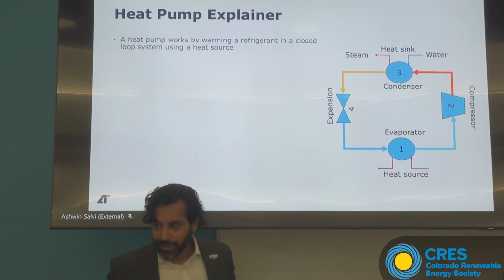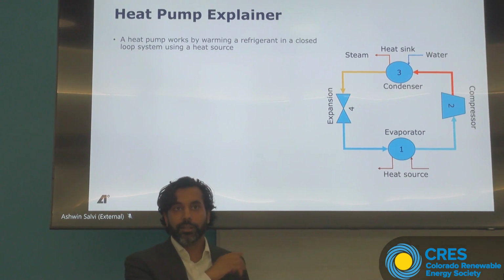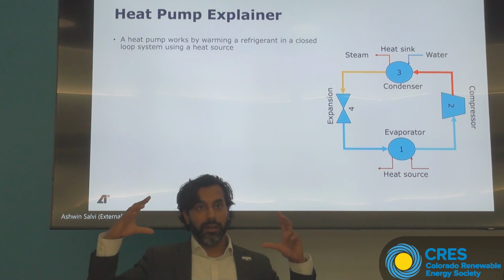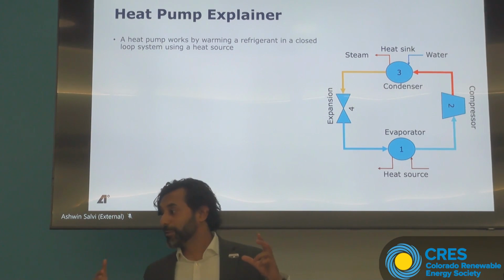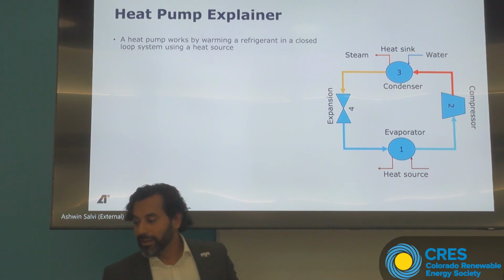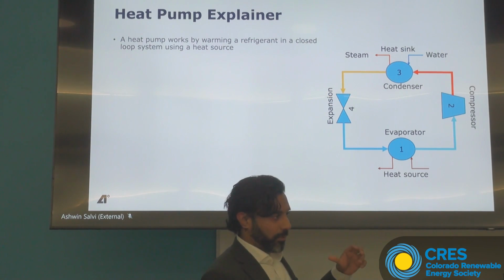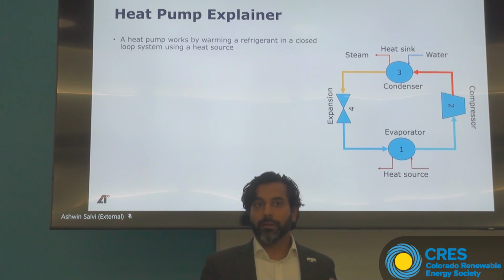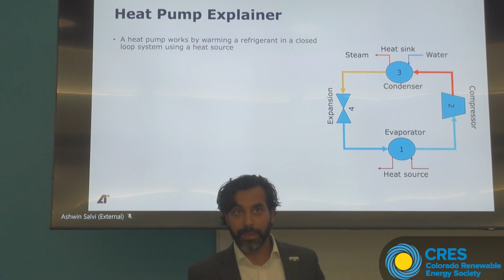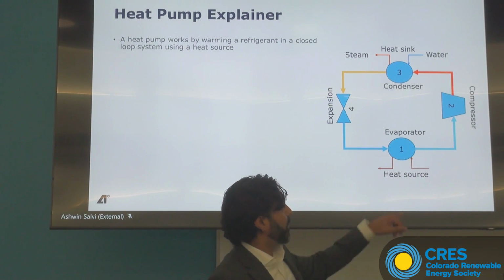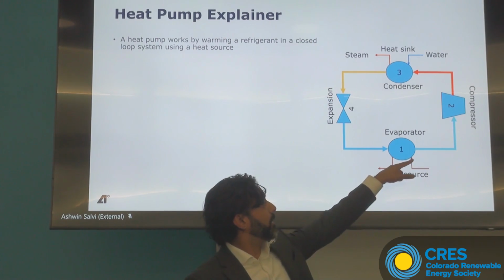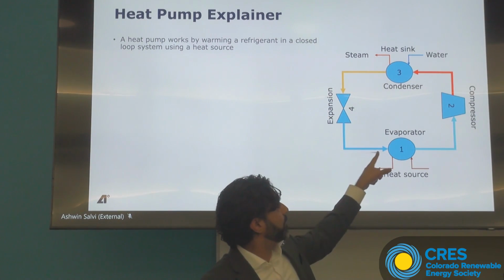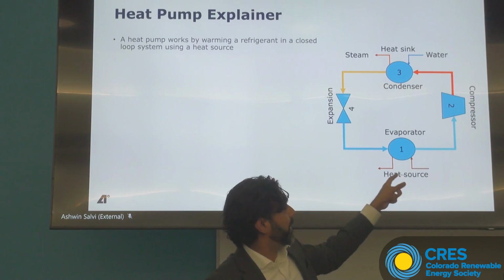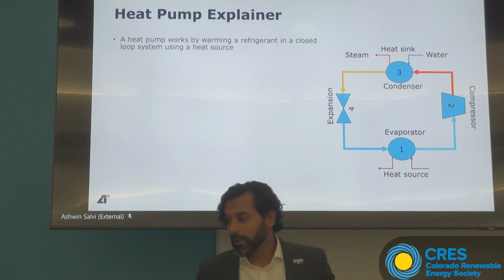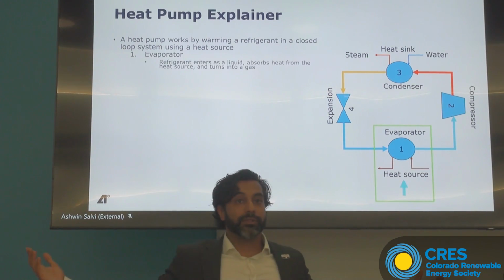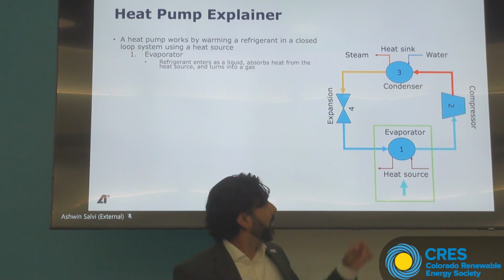So, sorry - a heat pump based system is a closed loop of refrigerant inside three or four different devices. Thank you for checking, or making sure I don't trip again. What we're doing here is sourcing heat from a certain location. Maybe a lot of you are familiar with air-sourced heat pumps that make hot water or something like that - they're pulling heat from ambient air. That air goes into an evaporator, which has liquid refrigerant coming in, and the heat from that heat source converts that liquid into a gas. So we absorb heat from a heat source, whether that's air or water or something else, and convert that liquid refrigerant into gas.